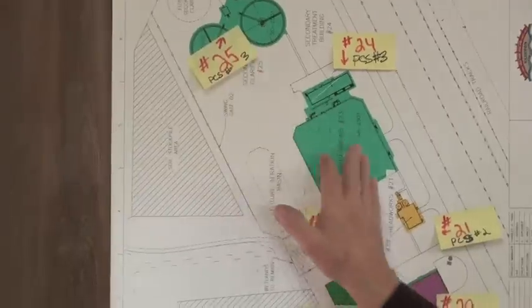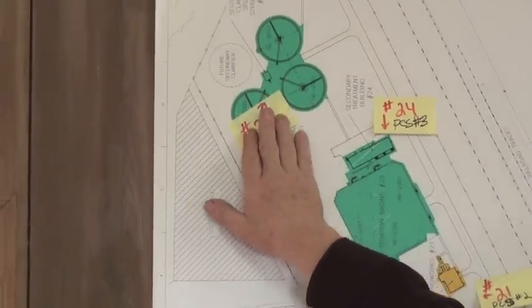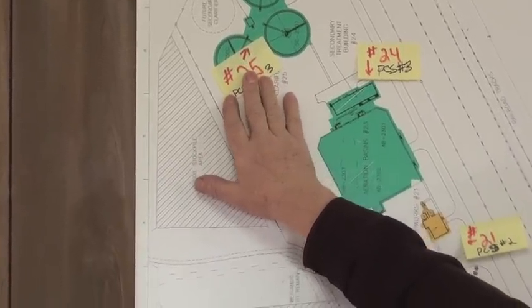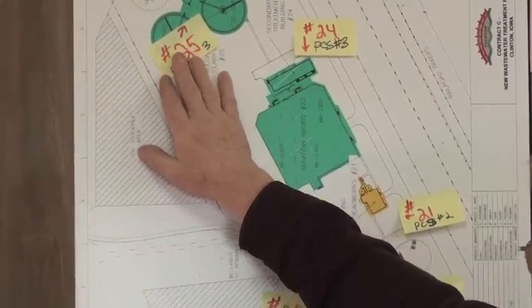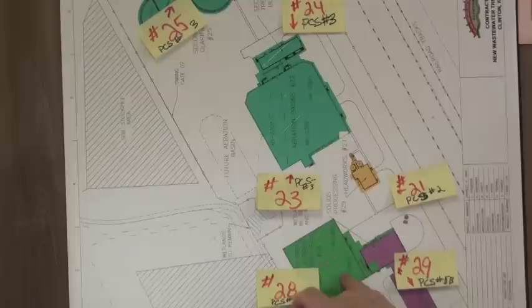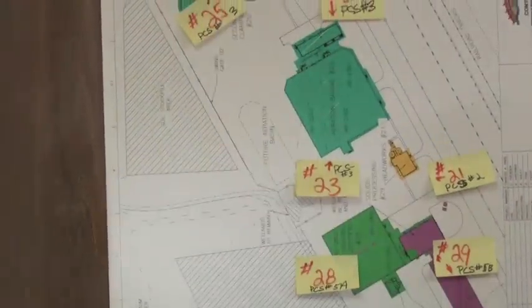Okay. And then after the water comes out of the aeration basins, there's still a small amount of solids in it. It goes to final clarifiers where the final, very light solids will settle out. There's a long detention time. The water will look like it's just sitting in there even though it's moving very slowly. But the solids that come off the bottom again get pumped back over here for digestion and further treatment. And then the clear water will come out to the pump station and be pumped back to the river.